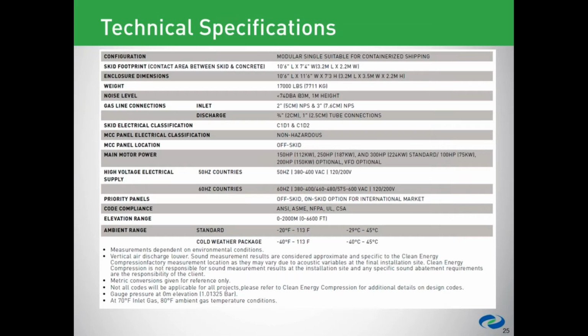Coming to you again, is the compressor liquid drain heated for cold climate installation? Do we know anything about cold climate? So the drain is internal to the compressor package, and in cold climates we install a space heater inside of the compressor package that's sized to maintain the internal temperature above freezing. So that will keep all your liquids, everything inside that package above freezing, allowing you to drain.